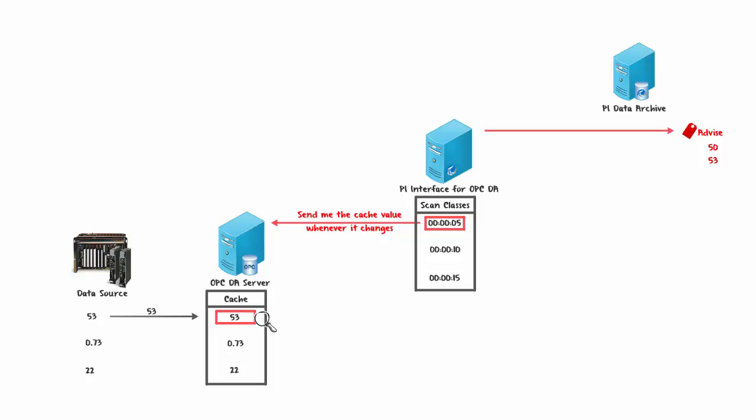After another arbitrary amount of time, if the Data Source updates, the Cache Value updates, and once again our Advise Point gets a new value. This is a really efficient way of getting data from the OPC Server, because the PI Interface made a single request and obtains all new values coming into the Cache. The scan class frequency — say 5 seconds — just limits how many values the PI Interface sends to the PI Data Archive, meaning it won't send more than one value every 5 seconds.